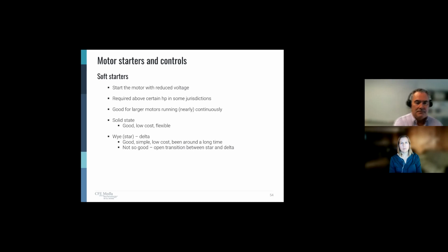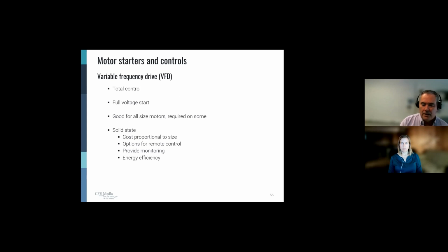A couple different types of soft starters: solid state, good, low cost, flexible. There's also the old mechanical type, which we used to call the delta, or the Y delta, or the star delta. Been around forever. The only disadvantage is there's a brief open transition as it switches, but typically for most applications, it's not a big deal. And then there's variable frequency drives, the latest and greatest. Total control, starts at full voltage, great for all size motors, just gets expensive as they get big. They can be controlled remotely. They provide monitoring, provide energy efficiency, good things all around.